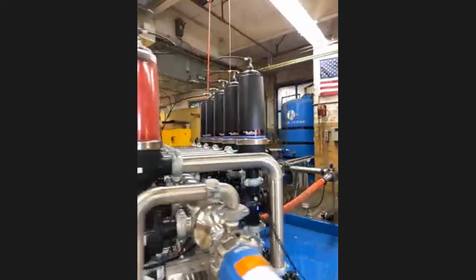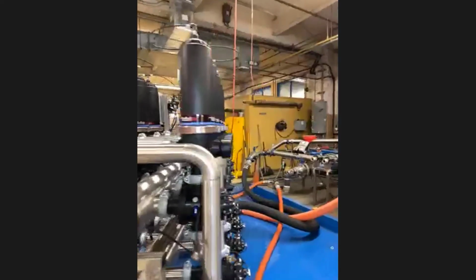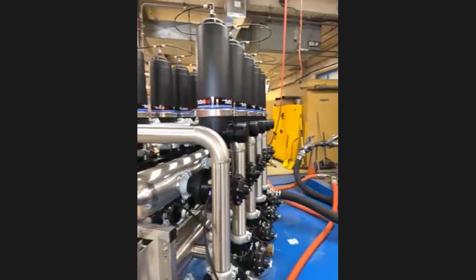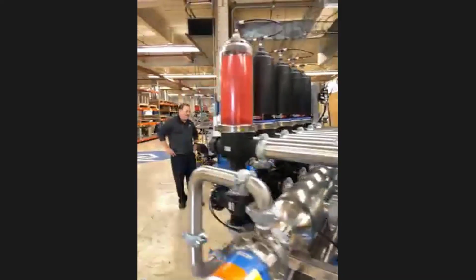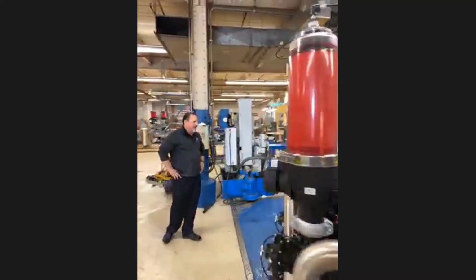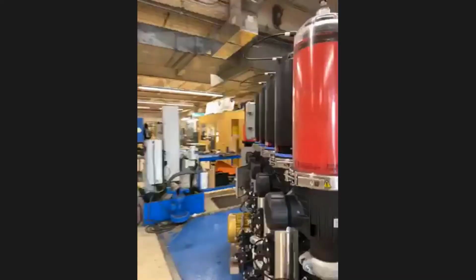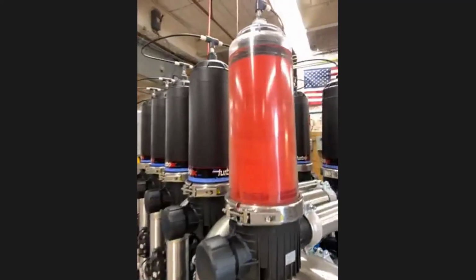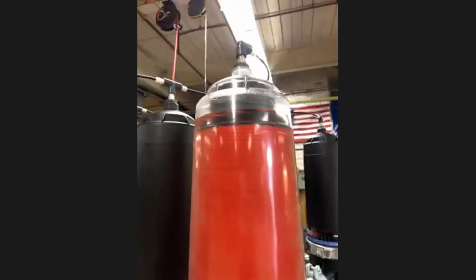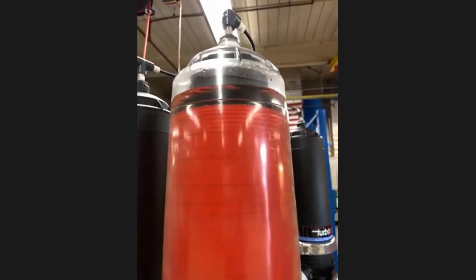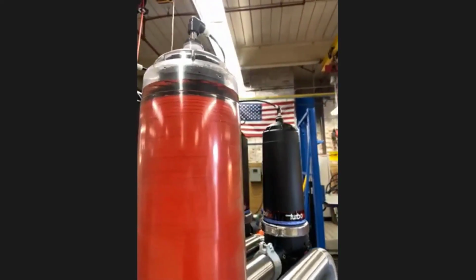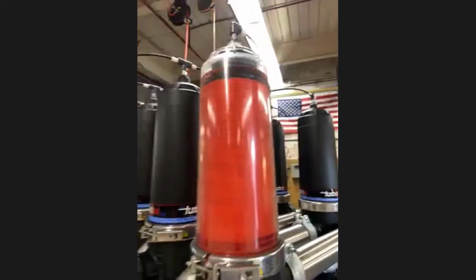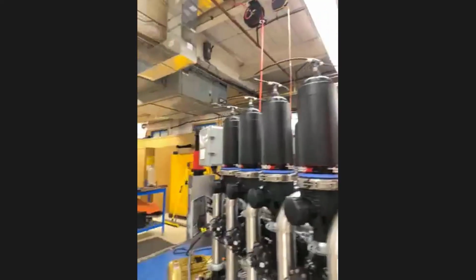Our units need compressed air to backflush. We actuate our valves with that, and we put a little bit of compressed air at the top of each pod. If we have to provide an air compressor, we would like to see them mounted inside just to protect that air compressor as well. But you know, 90% of the time, a lot of them are outside.